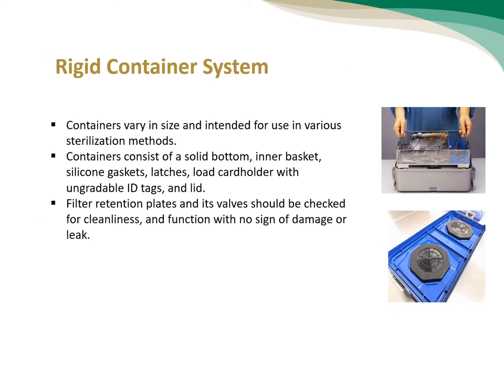The third type of packaging system is the rigid container system. Containers vary in size and are intended for use in various sterilization methods. The container consists of a solid bottom, inner basket, silicone gasket, latches, load card holder with changeable ID tags, and lid. The filter retention plate and its valve should be checked for cleanliness and function, with no sign of damage or leak.